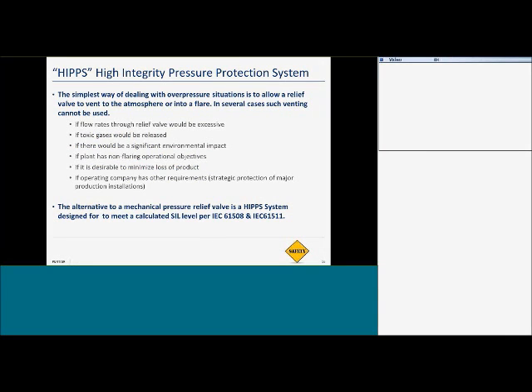Why would somebody install a high pressure protection system? So let's take a look at a few of the most common reasons. Typically, when you've got a high-pressure system, you've already got pressure relief valves in place to protect vessels and piping, etc. However, if the flow rates through those relief valves were excessive or could be excessive in certain conditions, they may want to install a high-integrity pressure protection system in addition to the relief valve.